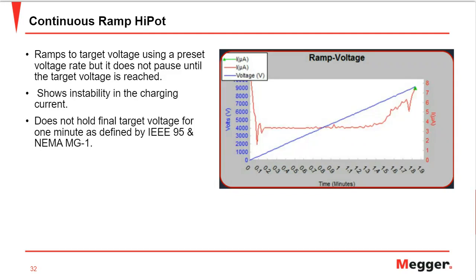So the slope of the curve should be fixed for a good motor. That is, the curve should be a straight line, since a higher voltage typically produces proportionally higher measured current. So again, in both the tests, we are looking at the linearity of the graph of the leakage current. So that's what it was about the hypot testing.